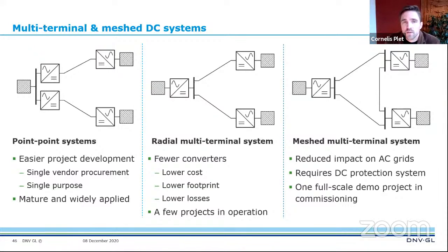Here we can reduce the impact of a DC fault on the AC system by rerouting power through a redundant path. This comes at the cost of needing DC grid protection in place, for example hybrid breakers or even hybrid converters, plus additional cable and cable capacity. It is technically possible - in China they are currently commissioning such a grid.